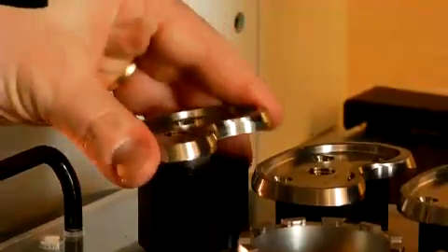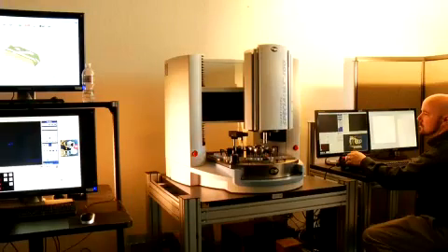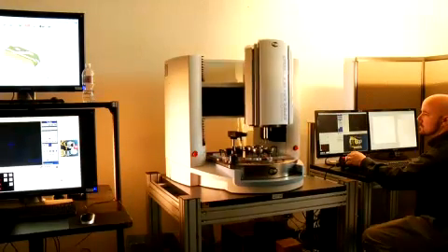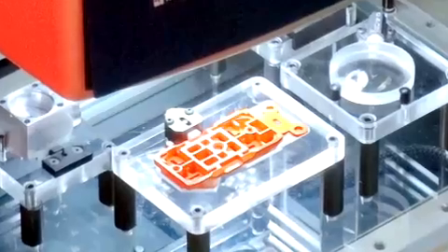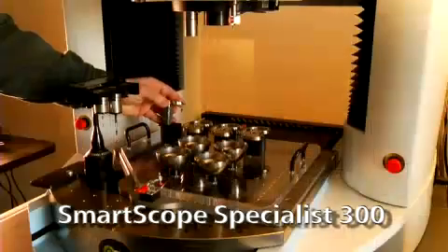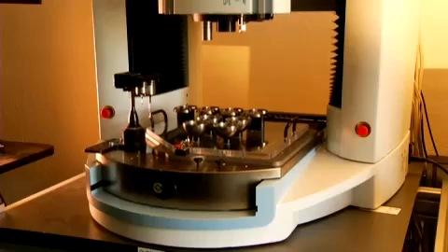A part like this may also have 3D requirements, in which case a multi-sensing system may have more appropriate tools and capabilities to acquire 3D data. One of the first considerations may be the size of the machine. There are several sizes available. Small machines are suitable for multiple small parts or one-up measurements of individual parts. The Specialist has a 12-inch by 12-inch by 10-inch volume, which is a popular size providing a small footprint.